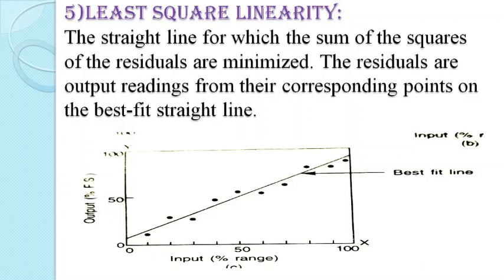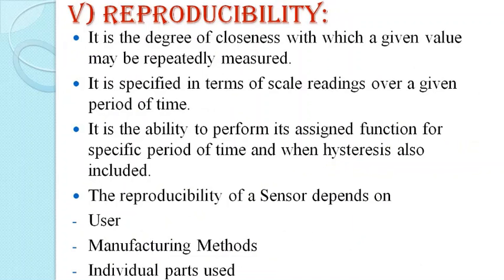The fifth type of linearity is least squares linearity. The straight line is one for which the sum of the squares of the residuals is minimized. The residuals are the output readings from their corresponding points on the best-fit straight line. The diagram shows how least squares linearity fits the straight line based on the residual output readings at their corresponding points.